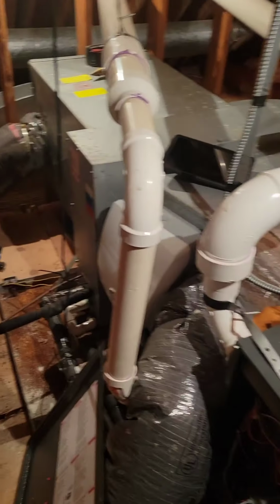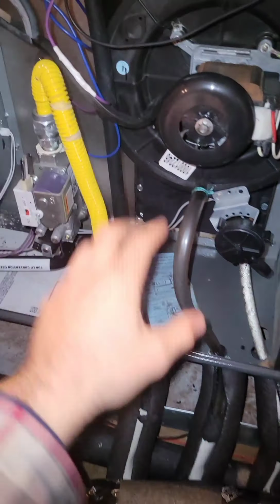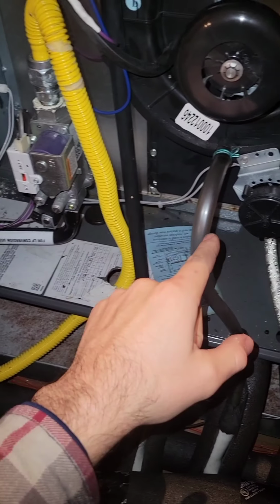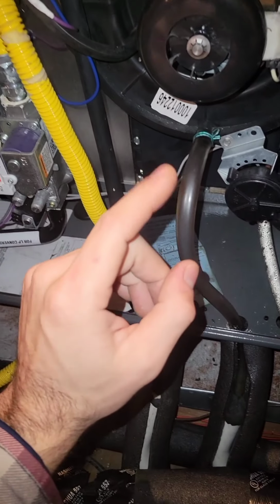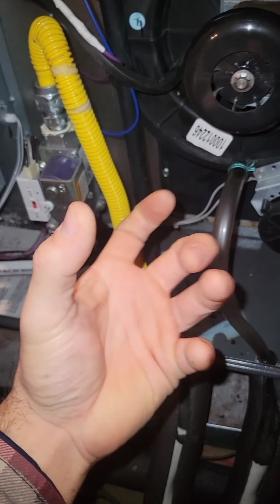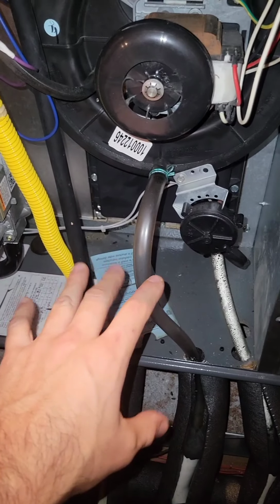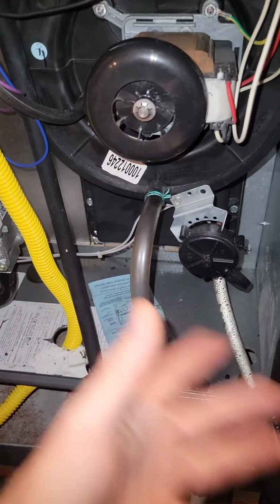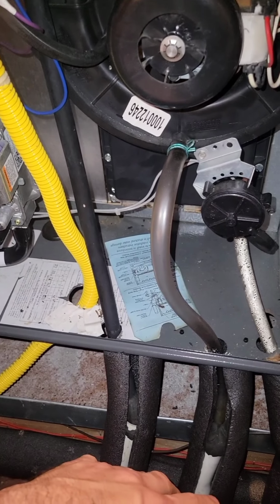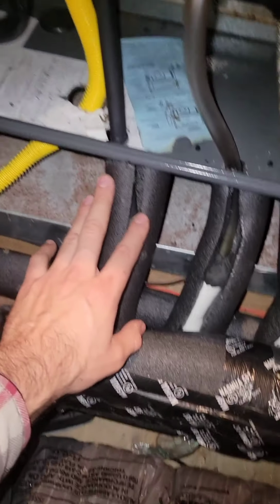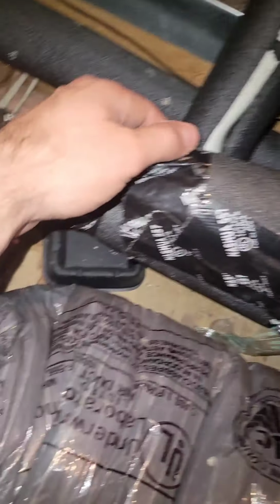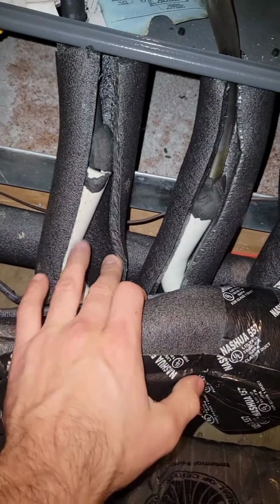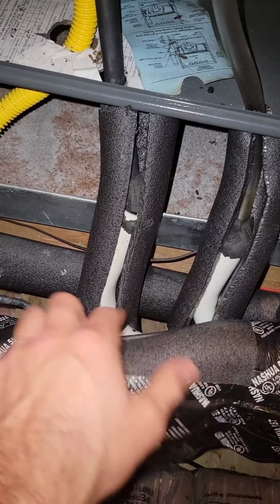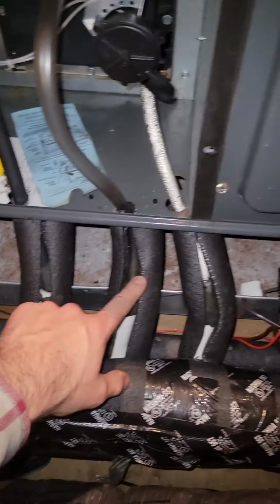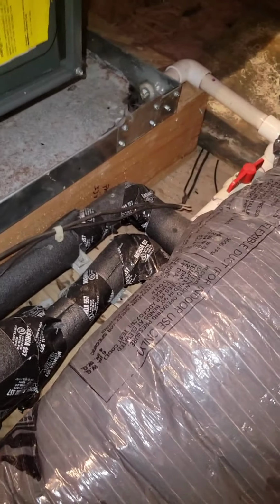They go outside. But if you take a look here at the furnace, there's the condensate line. If you remember on the one downstairs, there was a singular trap for all three of these, and they all went into a trap. The trap then went out to the main discharge on the pump, right? So in here, they individually placed a trap. You can see here it has a U-shaped bend on each one of these, going into a common pipe.